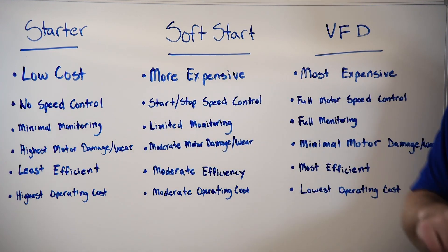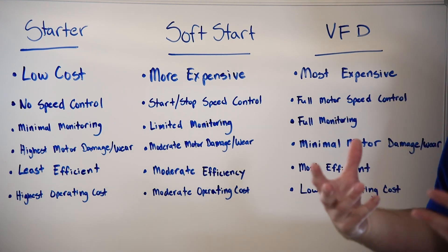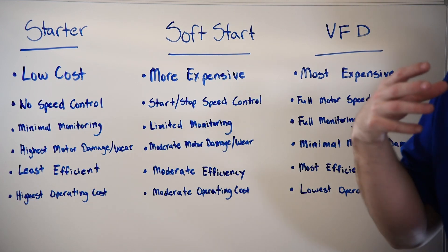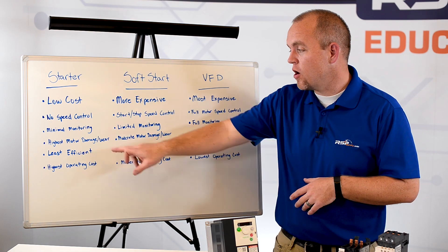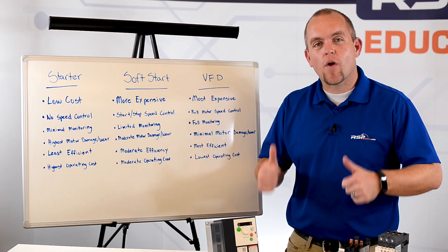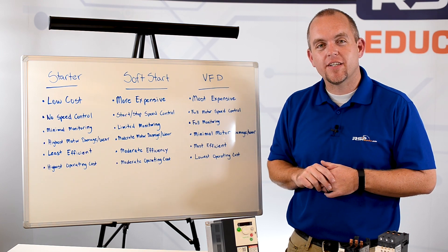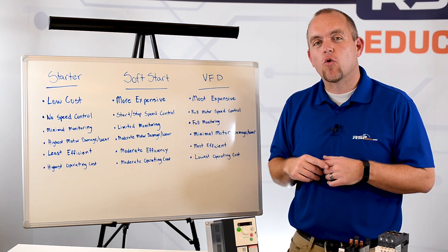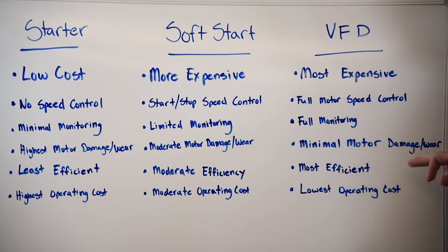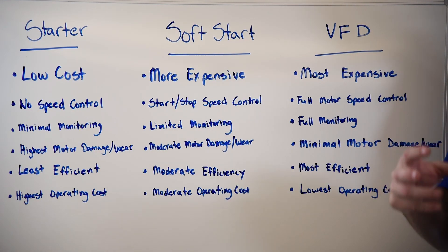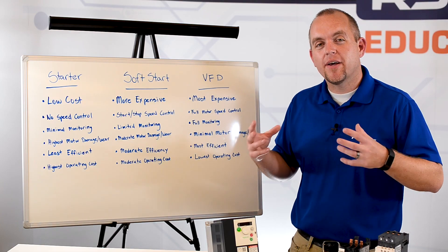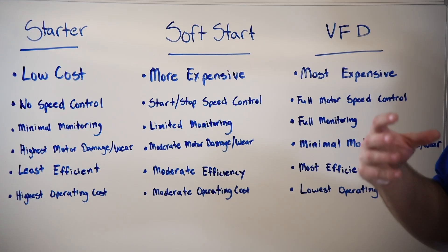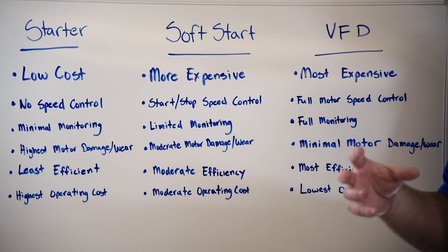Next, we have very little monitoring with a starter — maybe run status. A soft starter gives us a little extra monitoring if we need it, but a VFD gives us the ability to fully monitor our motor control. When talking about wear and tear on our motor, a starter is going to be the hardest on our motor because it ramps up so quickly and there's such a high inrush of current, causing the motor to degrade over time much more quickly. A VFD gives us very minimal motor damage and wear over time because of the control we have. A soft starter falls somewhere in between, allowing us to slowly ramp up only upon startup and in some cases upon shutdown.